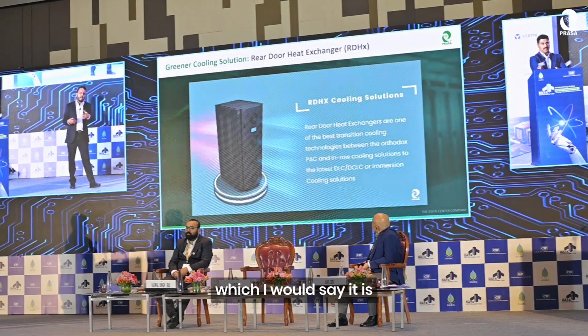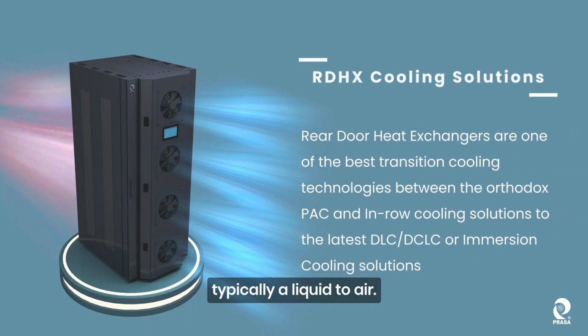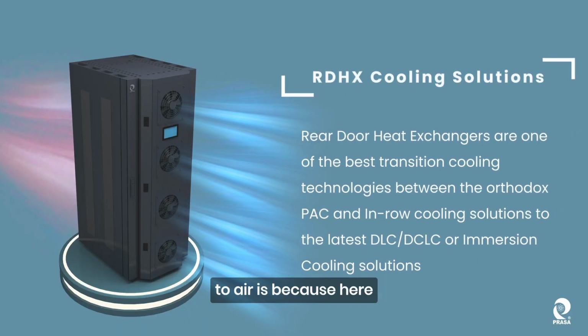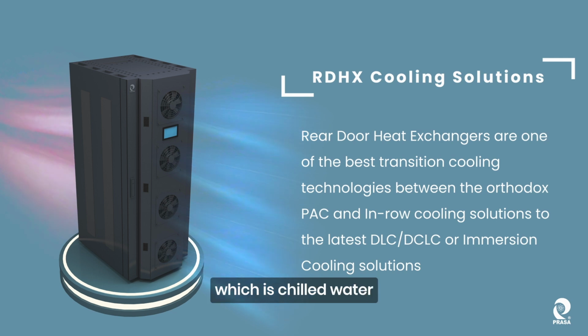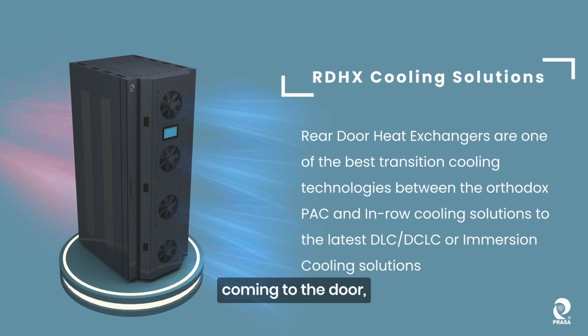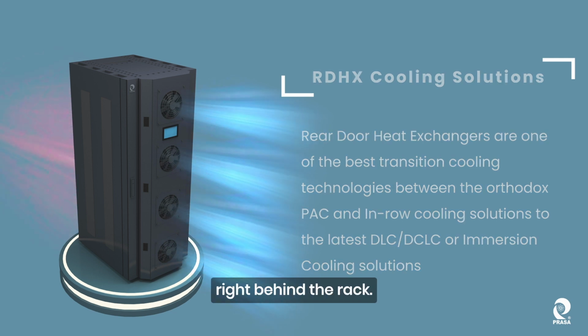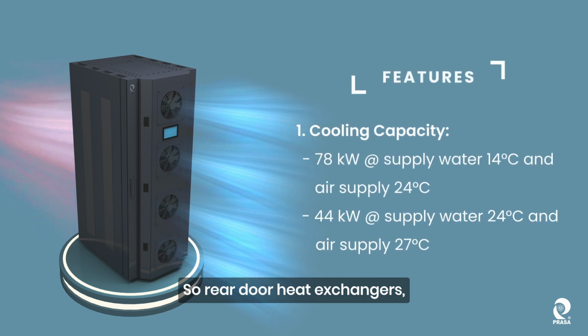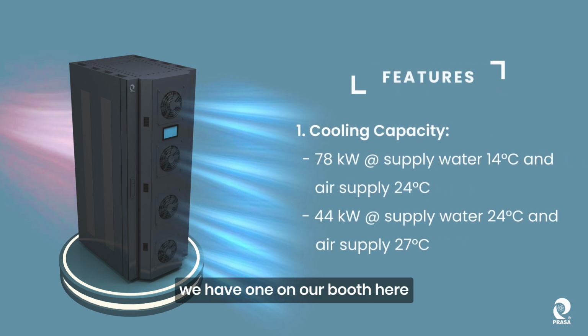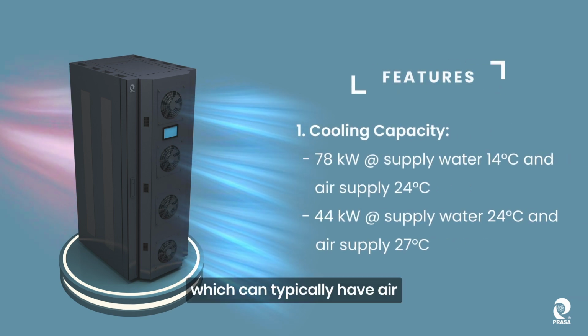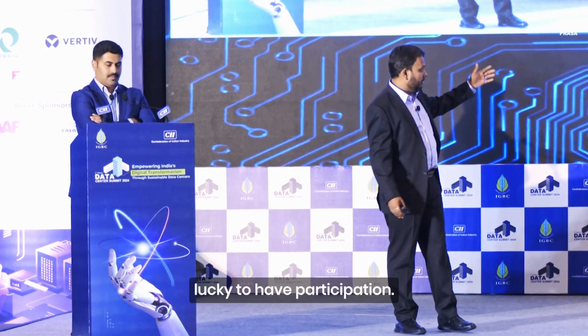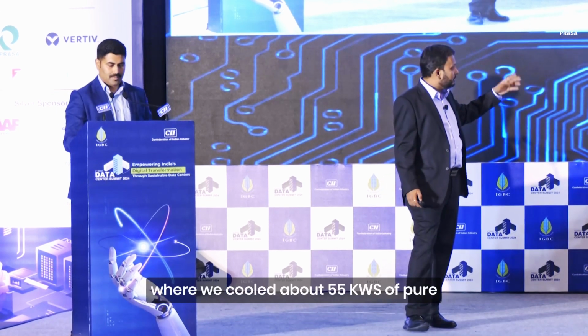Why would I call it liquid to air? Because here the liquid, which is chilled water, comes to the door, and the door sits right behind the rack. So rear door heat exchangers—we have one on our booth here—typically cool the air in a slightly more sustainable way.